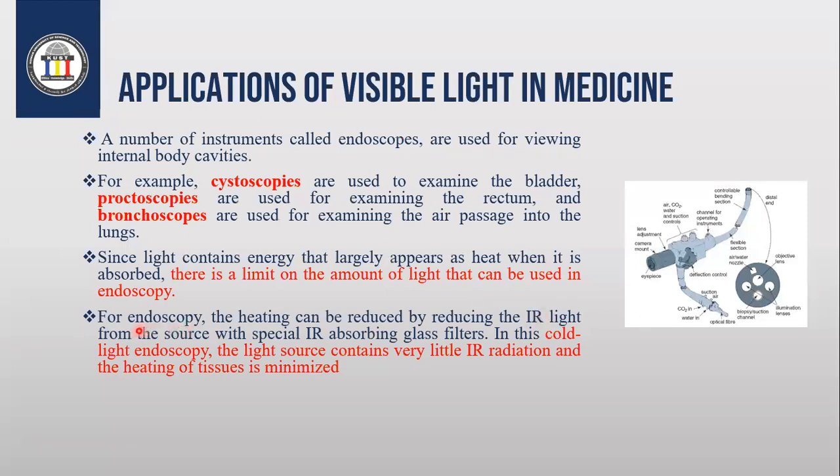I will make special absorbing glass filters, which will absorb or prevent the IR from passing through to the tissues. This is called cold light endoscopy. The light source contains very little IR radiation, and the heating of tissue will be minimized.